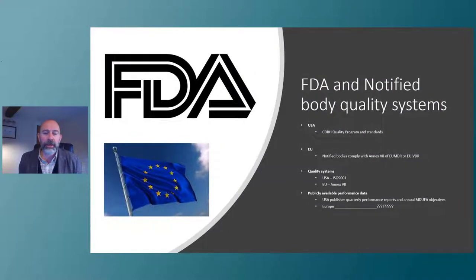I wanted to compare and contrast, be a little bit more present at this moment in time, and compare the United States regulatory system under the CDRH with that of what we're now seeing with Europe, and the designation of European notified bodies, in particular with the specific designation quality requirements that are imposed through Annex 7 of the new European Medical Device Regulations, and of course the European in vitro diagnostic regulations. And what we could see is that in terms of the quality systems, the FDA has...